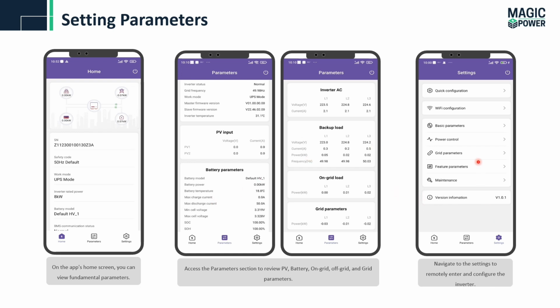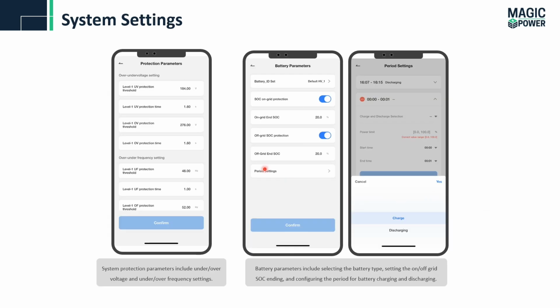Next, moving to settings. Here we can see the quick configuration. So it could be the operating mode of the system, some basic parameters, other power controls, and maintenance. In maintenance, we can remotely control our system; we can turn it off, or we can restart our system if it is required. Some other settings are for protection, for voltage protection, the minimum and maximum voltage. Similarly, for the frequency, minimum and maximum frequency, and the time.